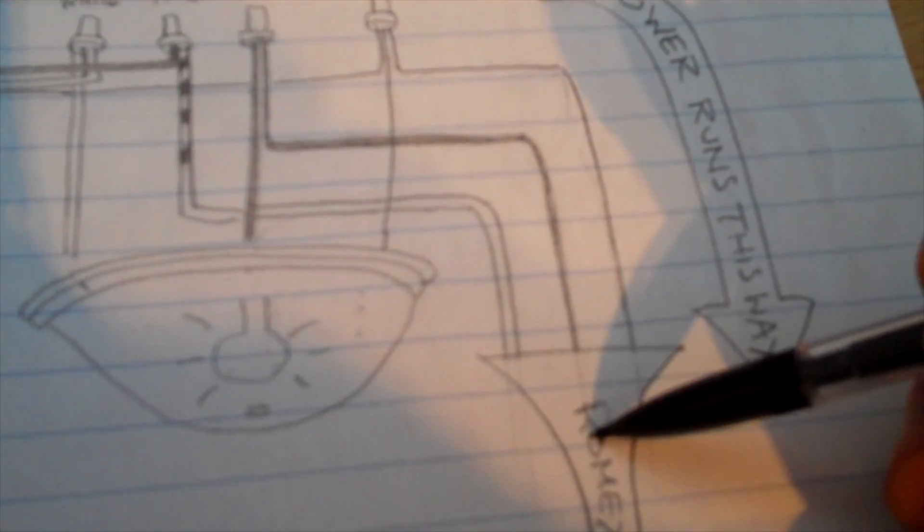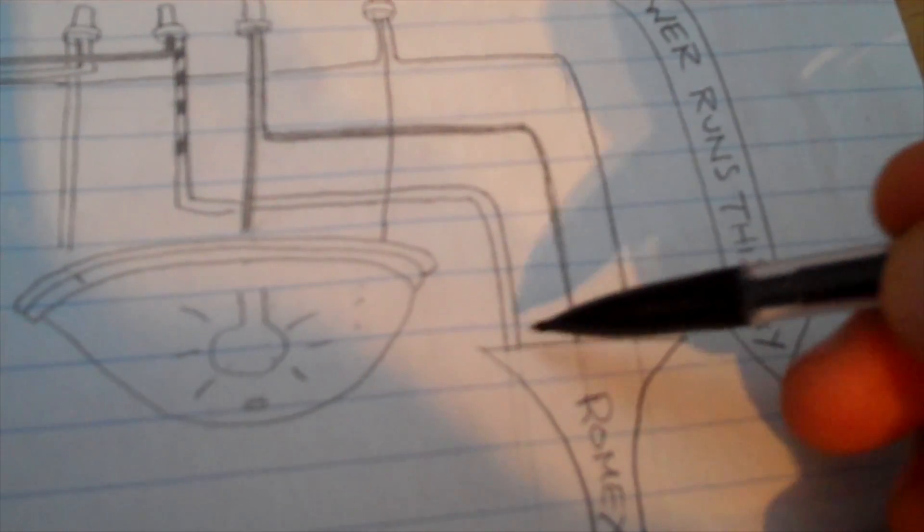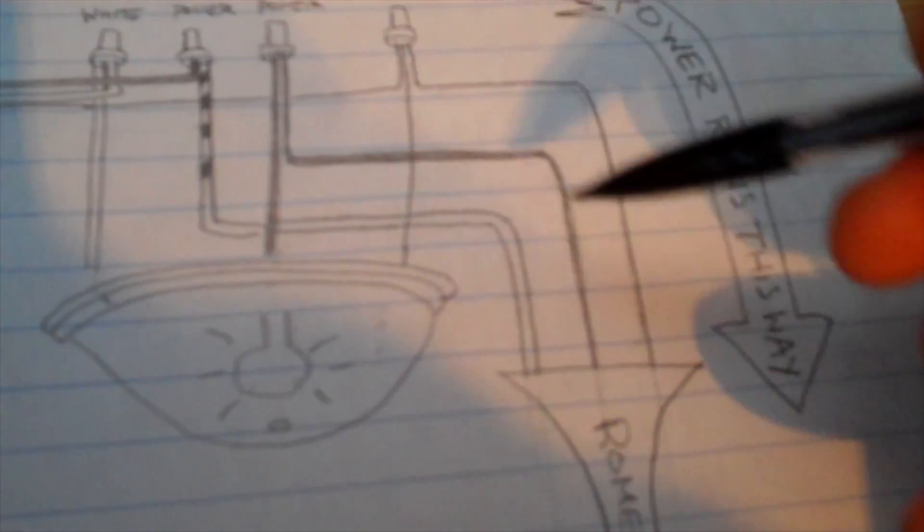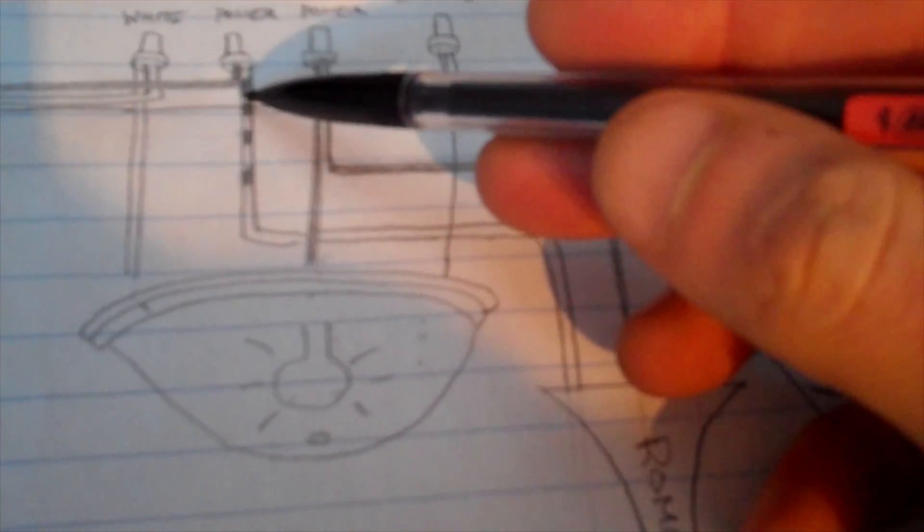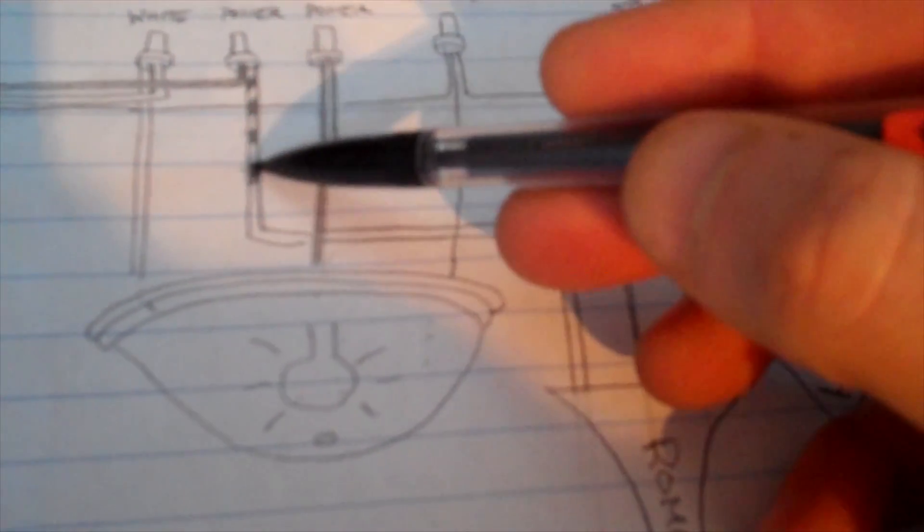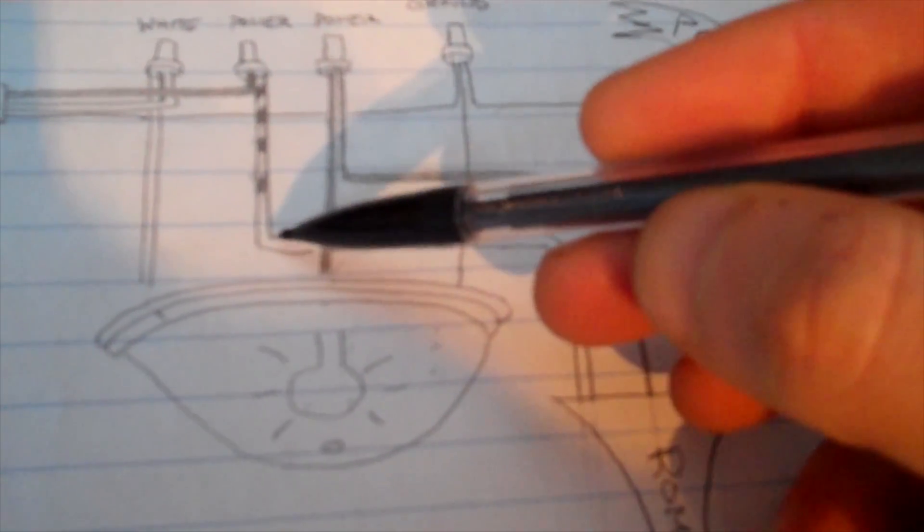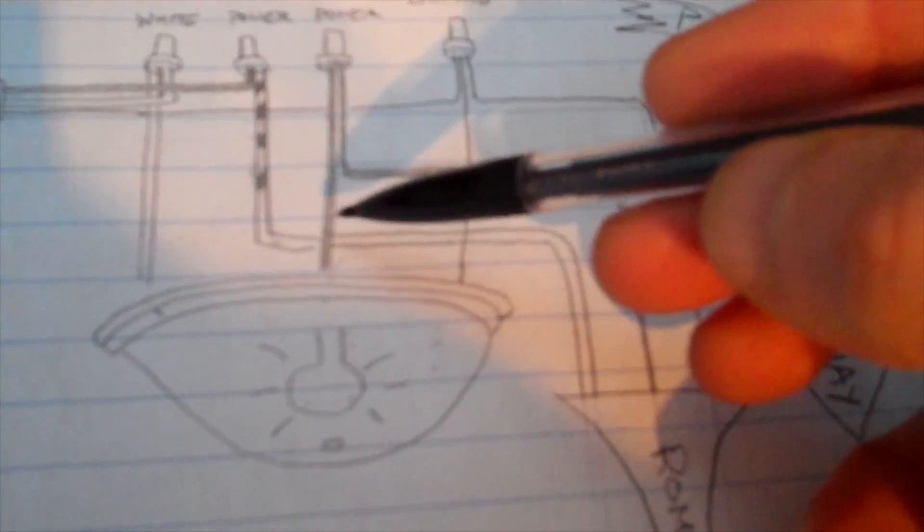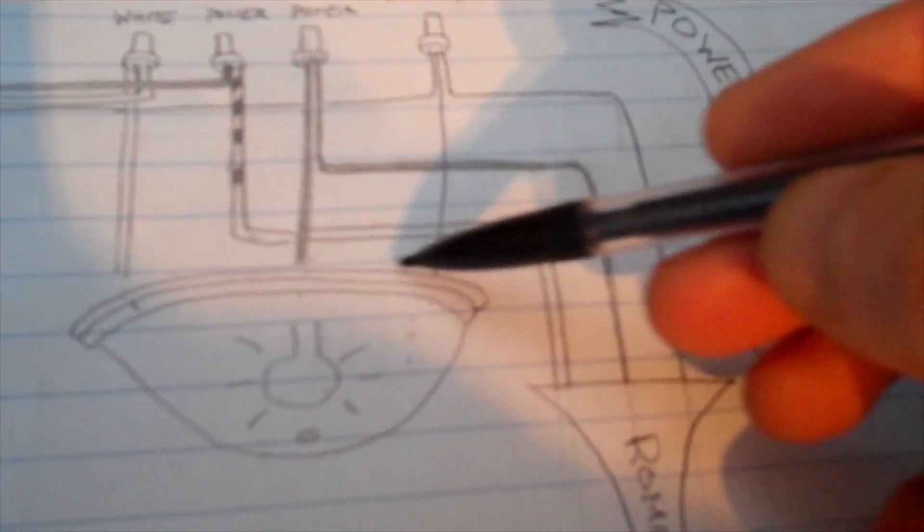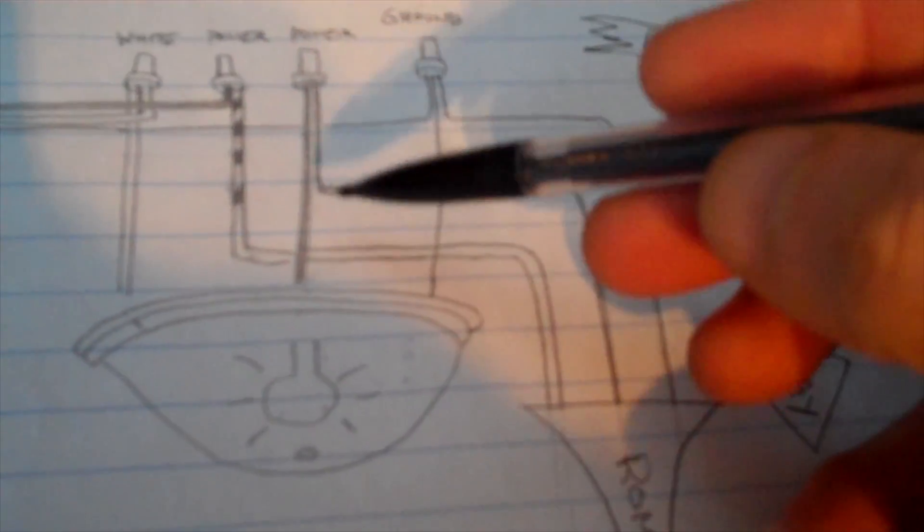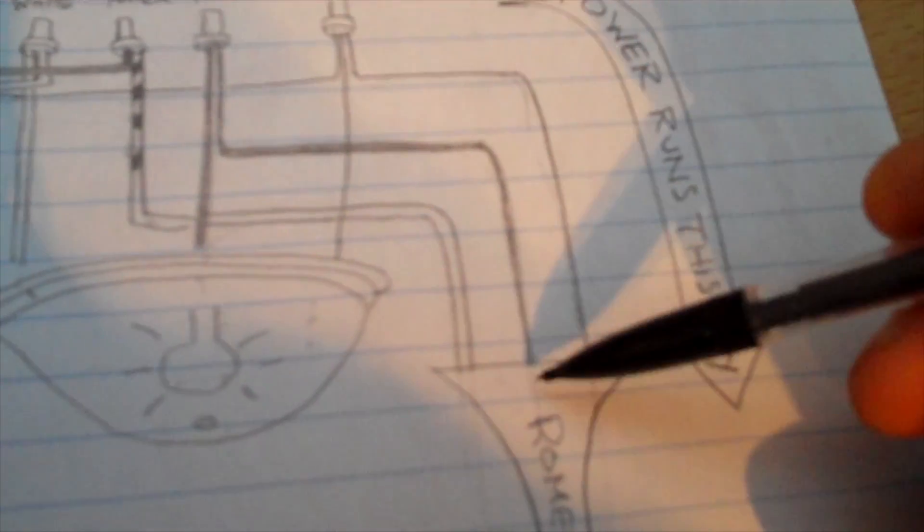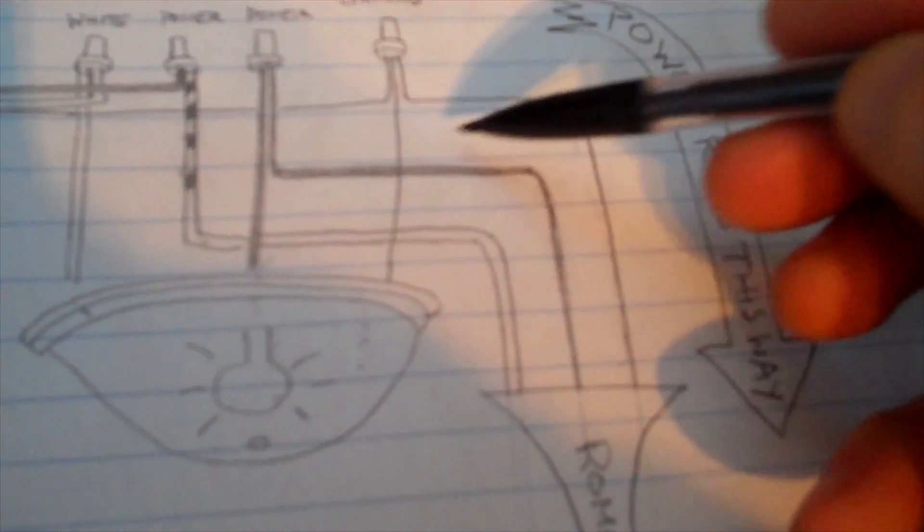So you have a new piece of Romex. It's got a white, it's got a black, it's got a ground. The white is tied together with a piece of black tape to tell a future electrician or yourself that something's funny with this switch or with this light. It's going to go to the Romex. The black is going to go from the light to the new piece on the Romex. The ground has been tied and that's going to continue on down the line.